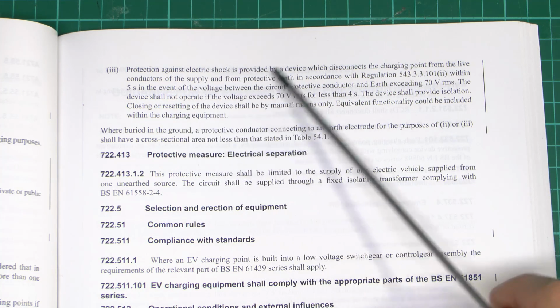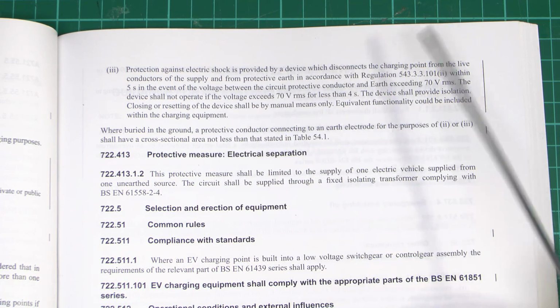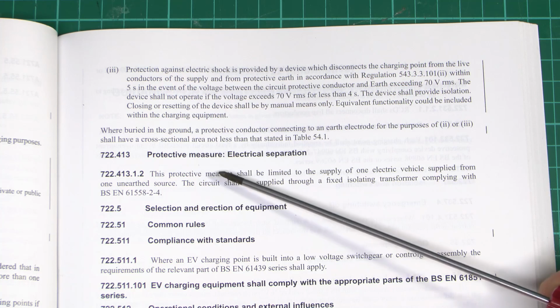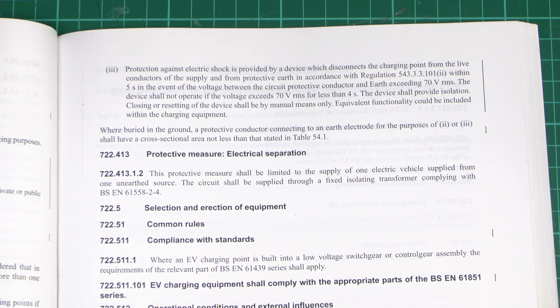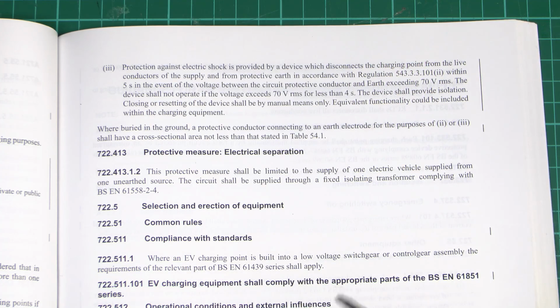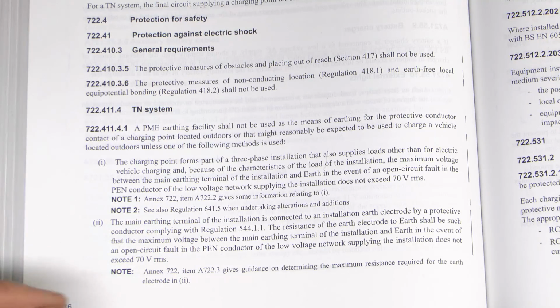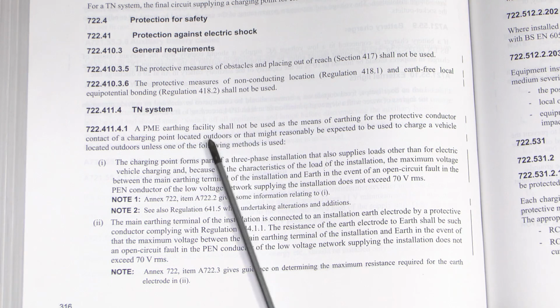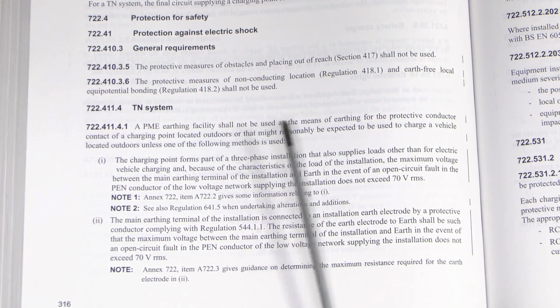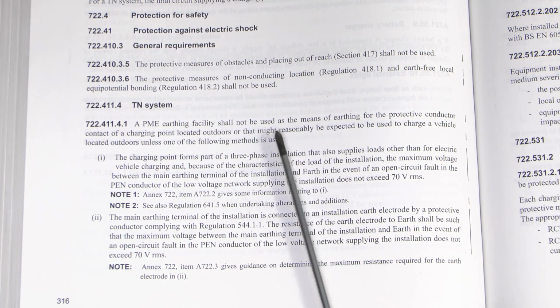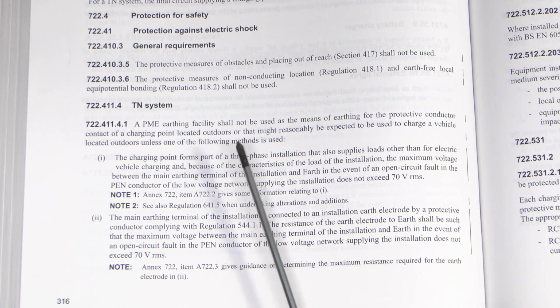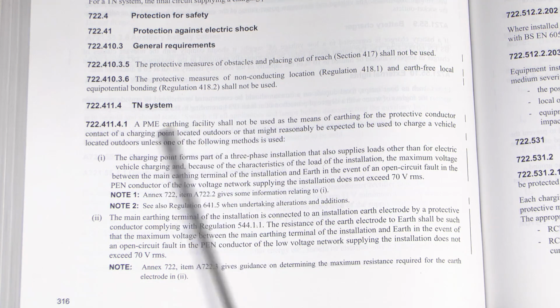So if you can get one of these devices and install it with an earth electrode and all the other gubbins it needs, then of course that's an option you could use. But at the moment it's not even something that's necessarily available, and even if it was, it's certainly not a trivial thing just to stick in there and make work. Now in reality what you're going to do if it is a TNCS system is to not use the PME earthing facility and instead install an earth electrode specifically for the car charging facility, connect that and use that as the earth connection for the charging equipment, and most importantly do not connect your earth electrode to the existing earthing facility for the building.